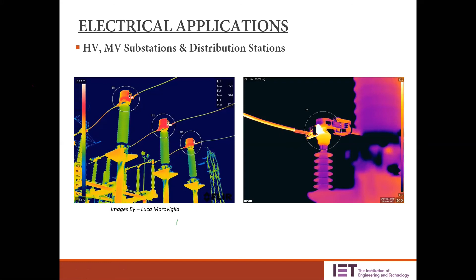So there are many components and many applications in electrical. You have breakers, you have bus bar systems, voltage transformers. Breakers, of course, you can monitor the contact points. You can monitor the internal contact strength. And the bus bar systems, of course, are tricky if they are naked. Like I said, shiny metals are low in emissivity. For bus bar systems, we highly recommend emissivity improvements through sleeves. There are heat sleeves, bus bar sleeves, which can significantly improve the emissivity of the bus bar, enabling later troubleshooting of possible loose connections or misconnections.